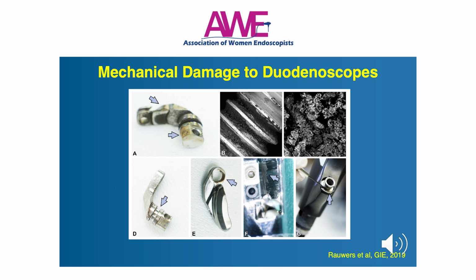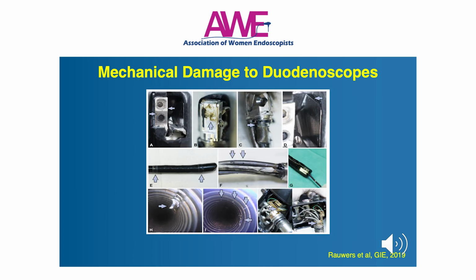We also see mechanical damage to the duodenoscopes. You can see a variety of damage occurs here, and we probably need to have a more rigorous process of sending scopes back for routine maintenance rather than waiting for them to have a failure or some imperfection that is visible. And here's some more channel damage that you can see on the inside, scratches to the channel, and you can see some areas of damage within the scopes that are not often appreciated initially.